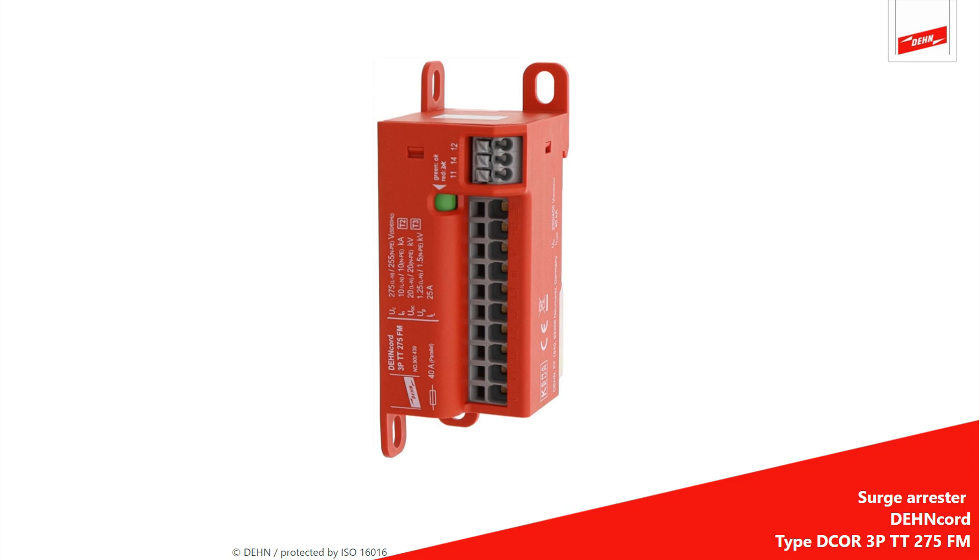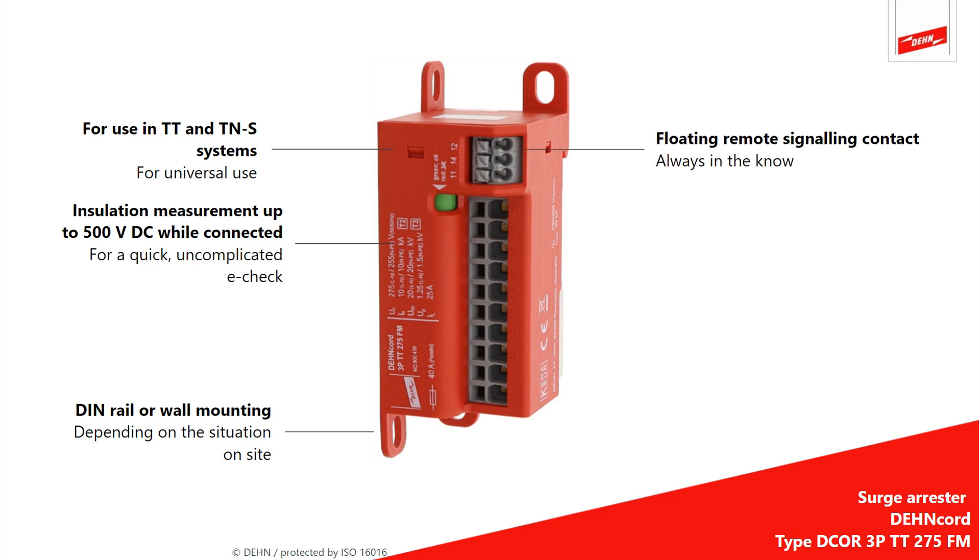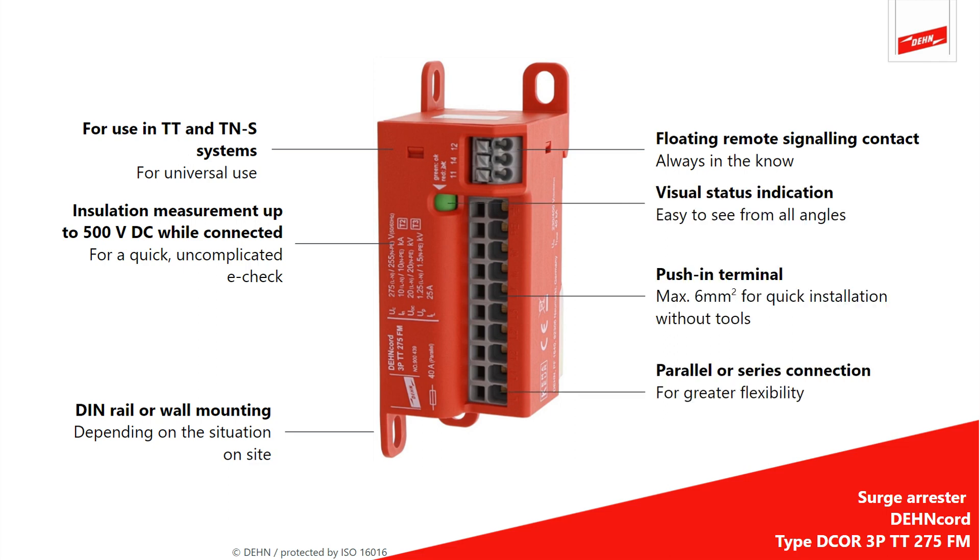Another advantage is that it can be universally used in all networks. An e-check is easily performed, even while connected. DEHNcord 3P can be mounted on the enclosure panel or DIN rail. You can see at any time whether the arrester is functional via the floating remote signaling contact and via the visual status indication directly on the device.